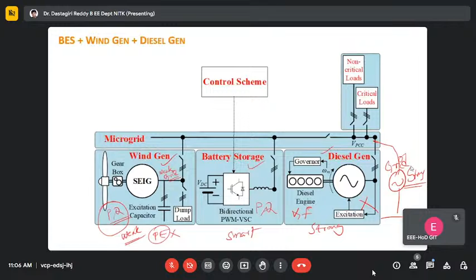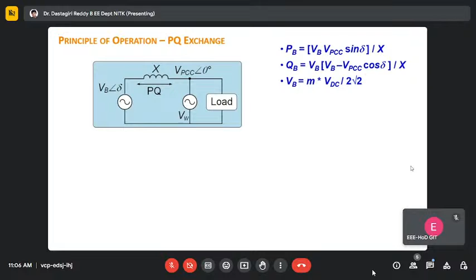Whatever I said in the modes, how exactly can we do that? It's very simple, a two machine theory. If you want to exchange P and Q, all you need is to control the voltage magnitude and delta. Based on these two simple formulas, if you want to exchange Q, your voltage should be higher than the PCC. But if you want to give power like P positive and Q positive, then your battery voltage or smart grid voltage should be higher than PCC, and it should be leading.